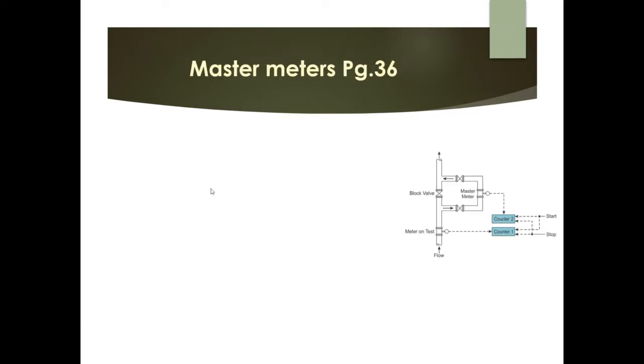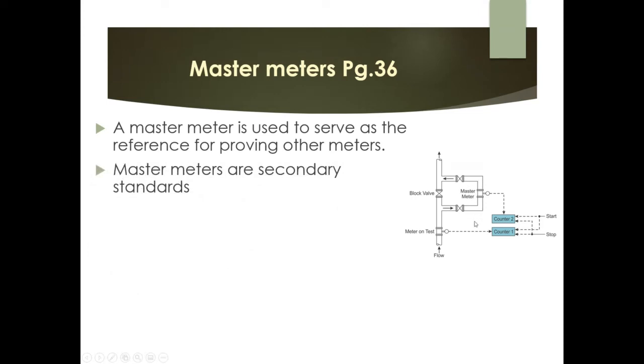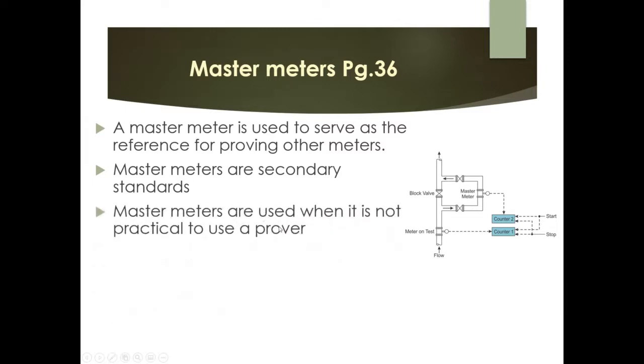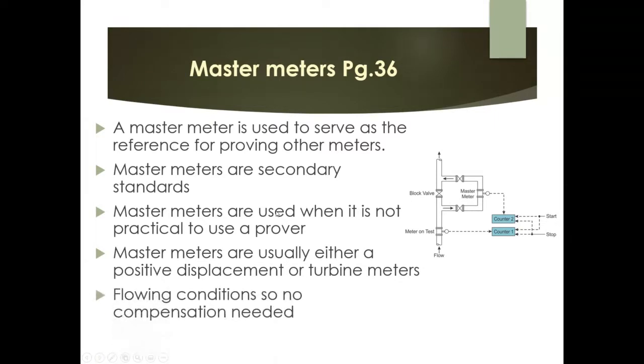Master meters serve as a reference for proving other meters. They are secondary standards used to calibrate daily meters, and are employed when it is not practical to use a pipe prover. Most master meters are either positive displacement or turbine meters. They are also used at flowing conditions by diverting flow, so no interruption occurs and no compensation for temperature or pressure conditions is needed.